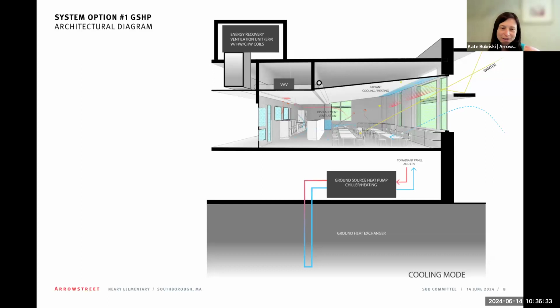Yes, the new code, technically, you can use it and it goes into effect. You can only use it after January 1st. It does still have a miscommunication between the IBC and, I think, the mechanical code. The industry is hoping to change that, but right now you would have to run those in the rated shafts. Even though the further IMC past 2021, I think it's 2024, does fix that, we're stuck with the 2021 because that's what we just adopted. So right now we have to assume that they would have to be in the rated shafts.